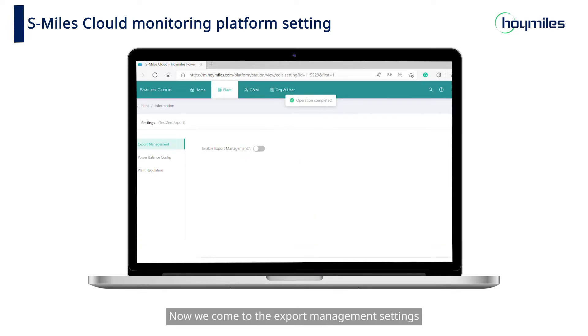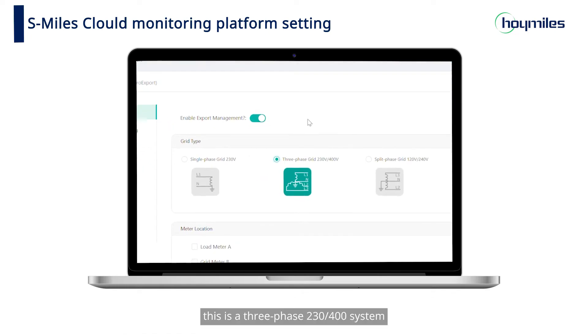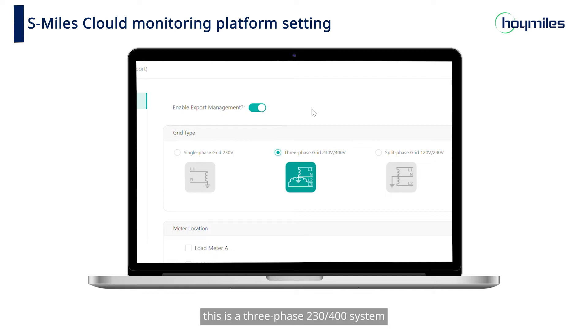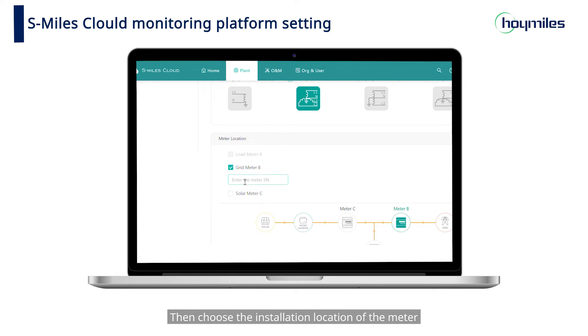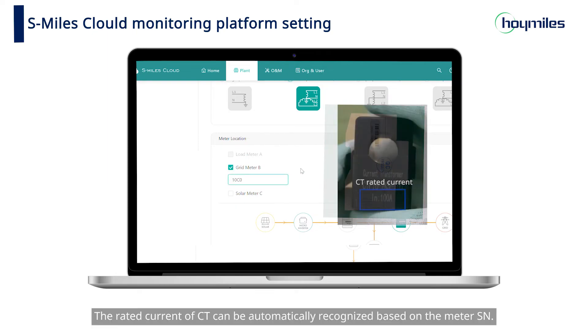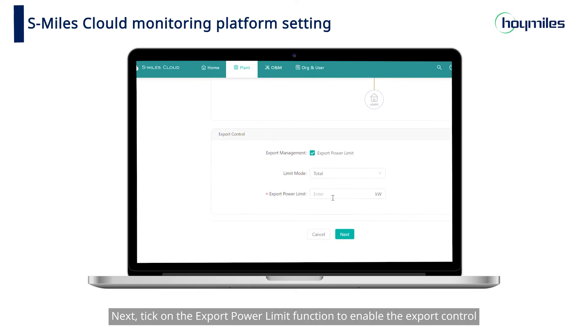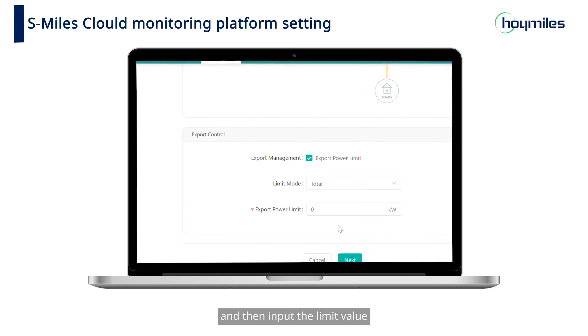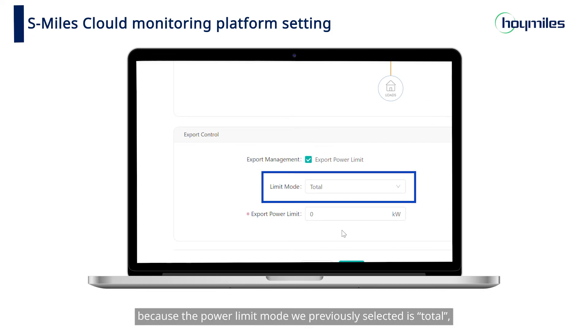Now we come to the Export Management settings. Switch on the slider button of Enable Export Management and you can select your grid type. In our case this is a three-phase 230/400V system — please select your own grid type. Then choose the installation location of the meter and type in the meter SN. The rated current of CT can be automatically recognized based on the meter SN. Tick the Export Power Limit function to enable export control and then input the limit value. We don't need to set the limit value of each phase because the power limit mode selected is total.